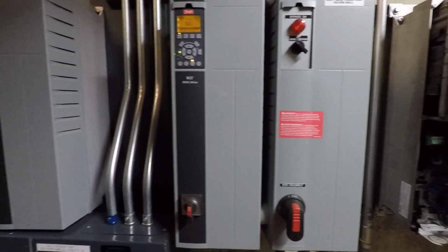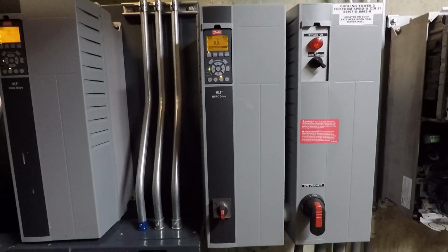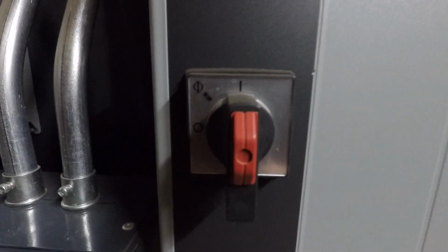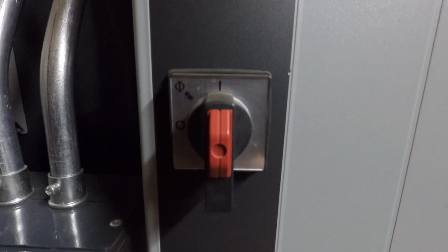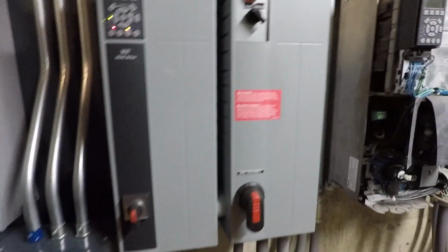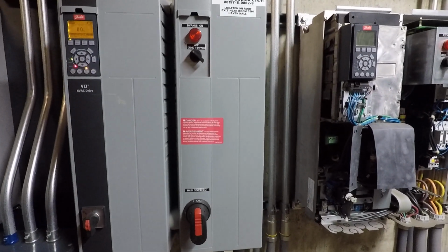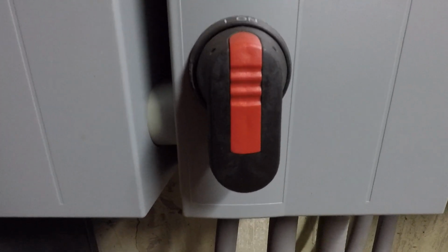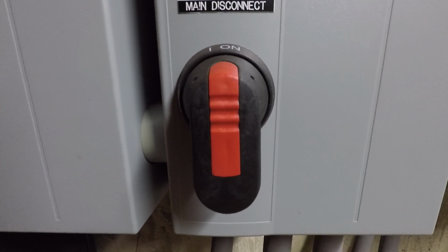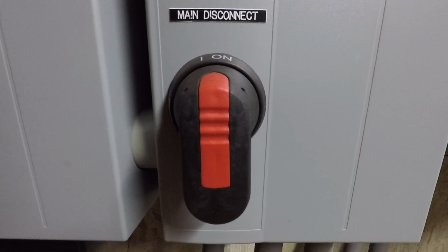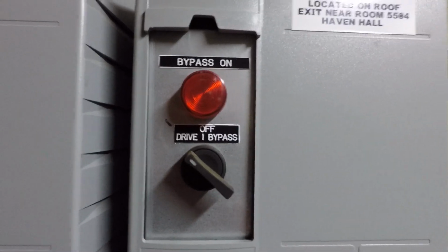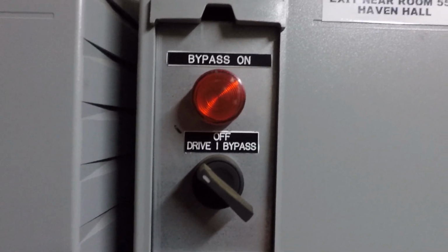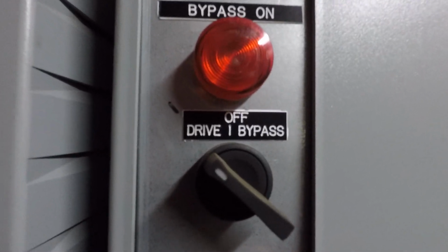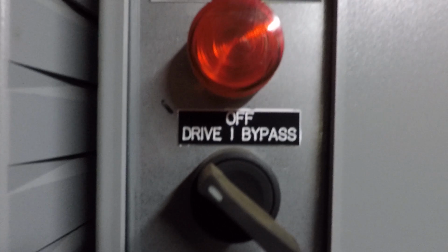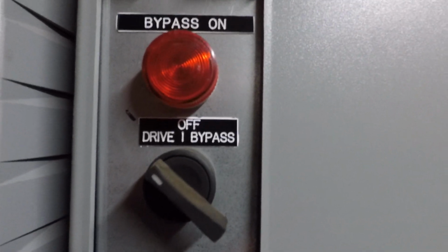So you will notice that the drive is on the left and it has a disconnect switch to disconnect the drive power, and then you have the bypass cabinet on the right, and you have the main disconnect switch that kills everything, kills the drive and bypass portion. Up here you have a pilot light to indicate if you're in bypass, and then you have a drive off bypass switch. That's the only controls you have that are hardwired.